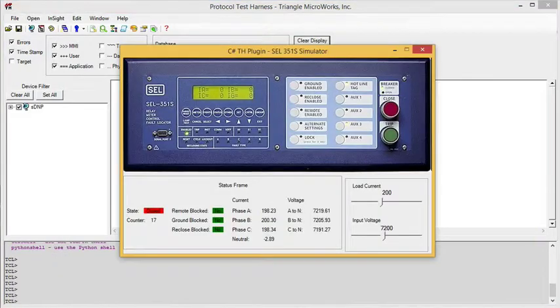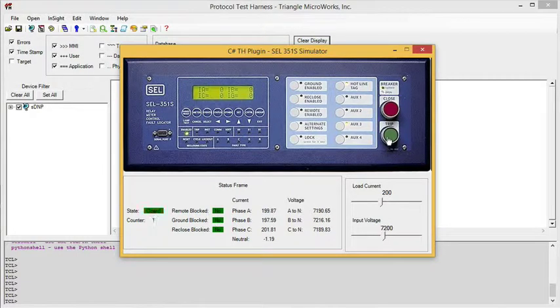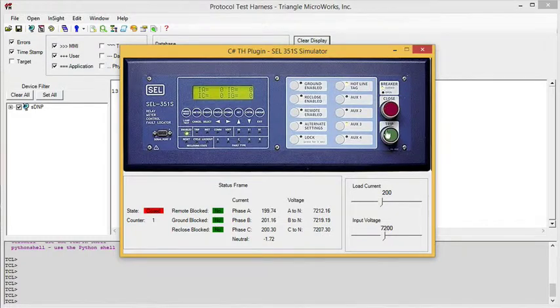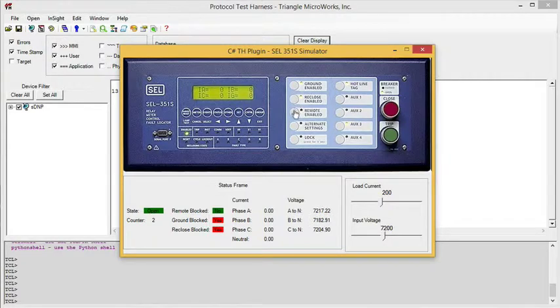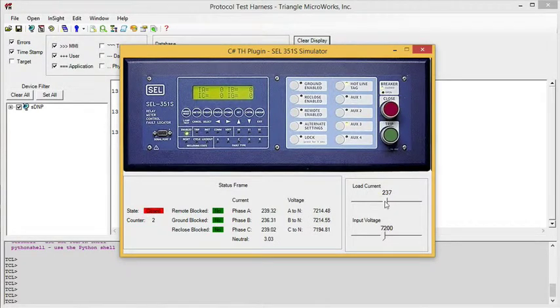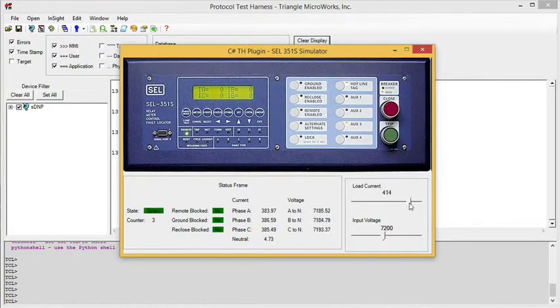And here's our front panel. Like the ABB simulator, the trip and close buttons work, and the status shows on the little LED there. We can enable ground, reclose, and remote. And this also has the simulation, so if we move the current up too high, the breaker will open.